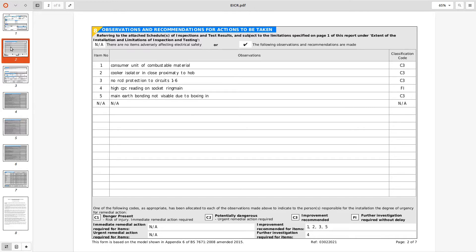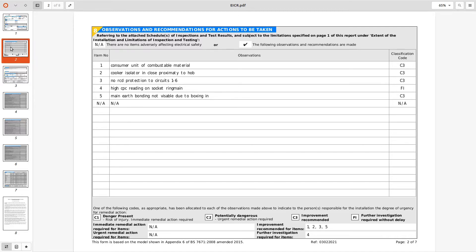It's presumably a split load board, latter circuits being RCD protected, so C3 that seems reasonable. High CPC reading on the socket ring main, oh very poor terminology, ring final circuit would have been better words, further investigation that's presumably end to end high resistance readings.